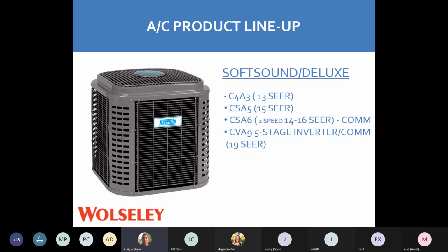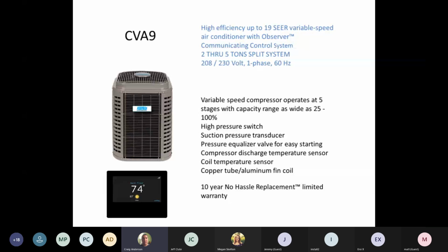So the next one is the upscale unit, a little better cabinet. Some of these have 2-speed fan motors on them. 13 SEER to 19 SEER on these units with communicating capability as well. So this is the communicating modulating AC that you guys will be installing or have installed already. So this unit is 5-stage modulating, as long as we're putting it on with a communicating furnace and a communicating stat. Everything needs to be communicating for this unit to be a modulating unit or a 5-stage unit.